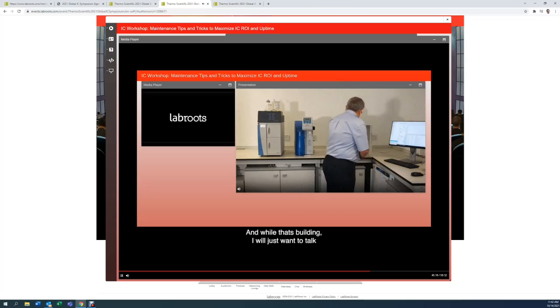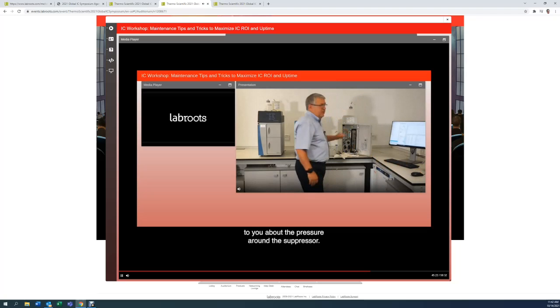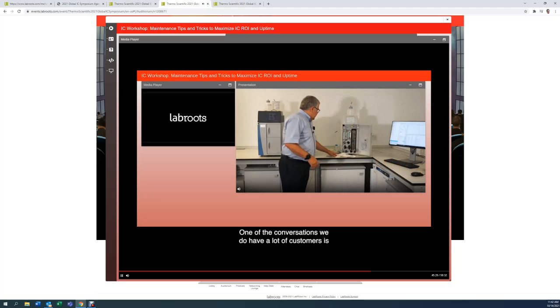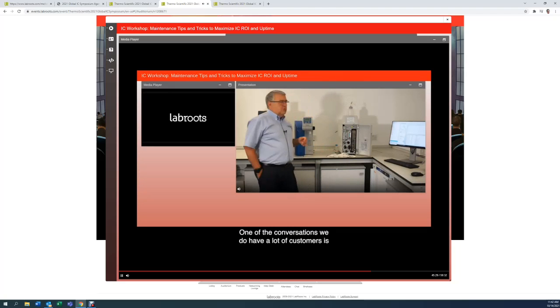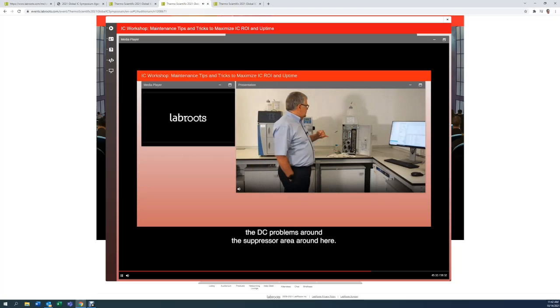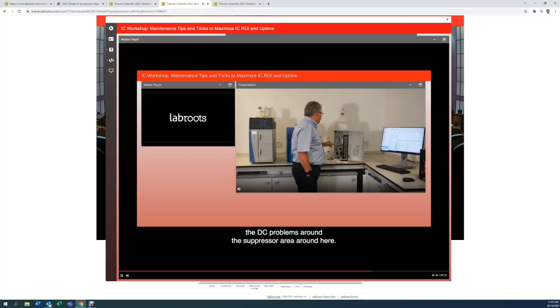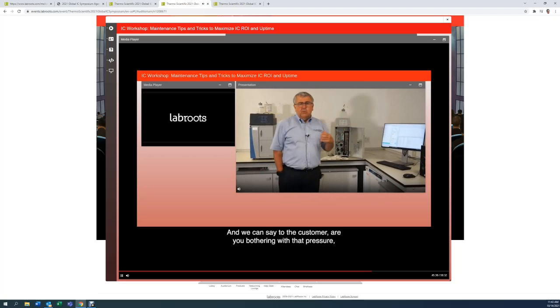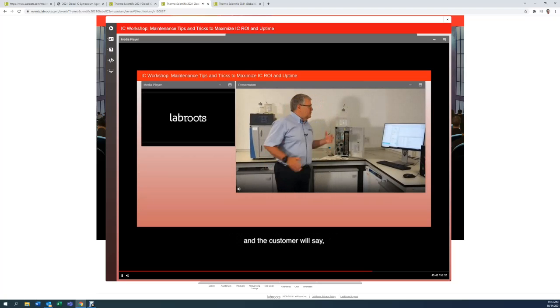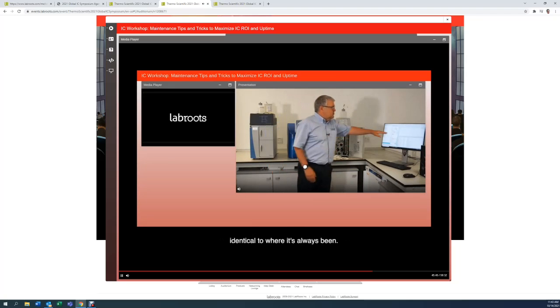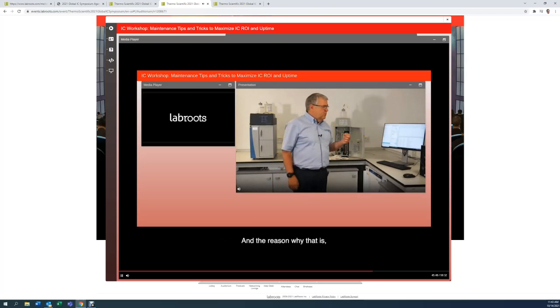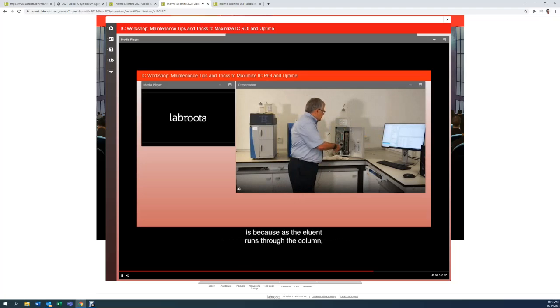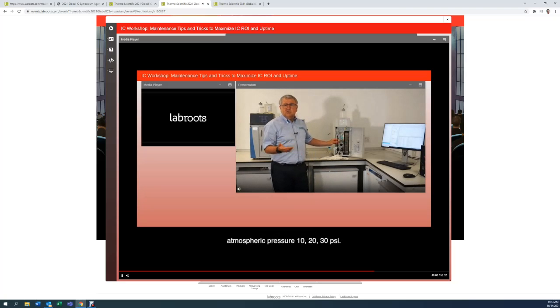And while that's building up, I just want to talk to you about the pressure around the suppressor. One of the conversations we do have with a lot of customers is they see problems around the suppressor area around here, and we can say to the customer, oh, you've got too much back pressure, and the customer will say, we haven't, because the back pressure is identical to where it's always been. And the reason why that is because as the eluent runs through the column, we see a massive pressure drop off. So although the pressure here is probably 2000 psi, by the time we get to the end here, it's effectively atmospheric pressure, 10, 20, 30 psi.